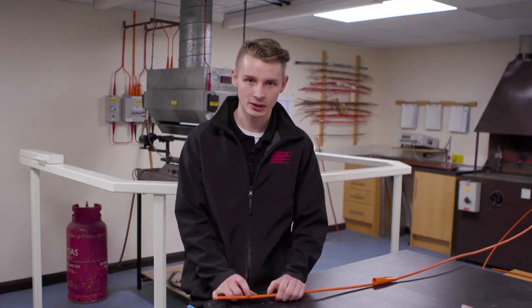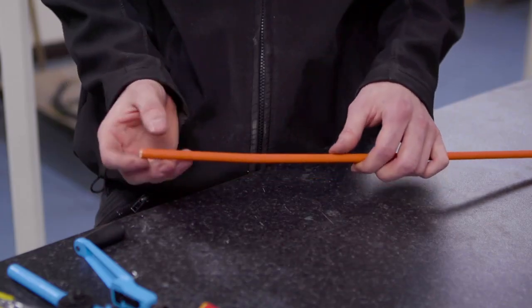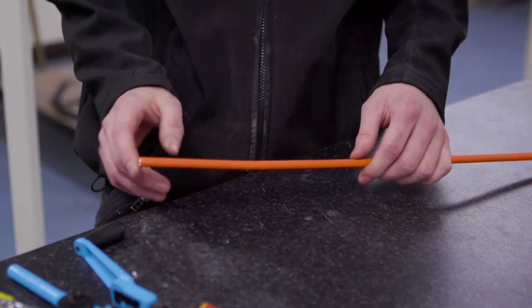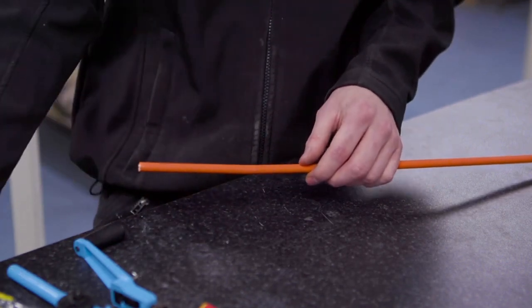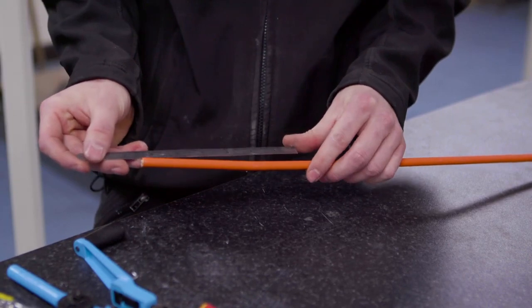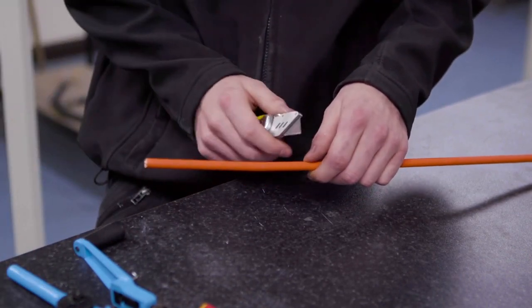Our next step is to remove the optional orange outer LSF sheath from the copper sheath. Mineral cable is known to draw moisture, however, the amount of ingress will only ever reach around two inches. By following our termination procedure and removing six inches of copper sheath, you eliminate all potential moisture issues, providing of course you complete the termination within a reasonable time frame.